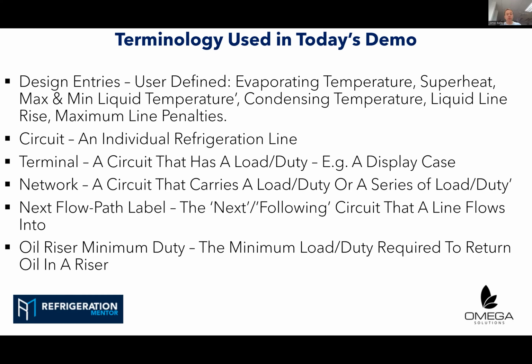So it's really cool because we can input a minimum duty for oil return. So oil return problems are commonplace, and not necessarily from a design engineer's perspective. This is more aimed at service technicians. The amount of times I've seen so much oil in systems, because ultimately a service technician gets called out, compressors tripped on low oil, top some oil back in.